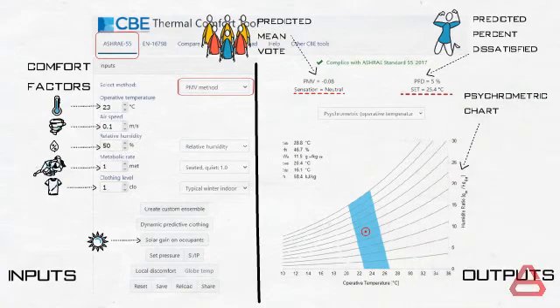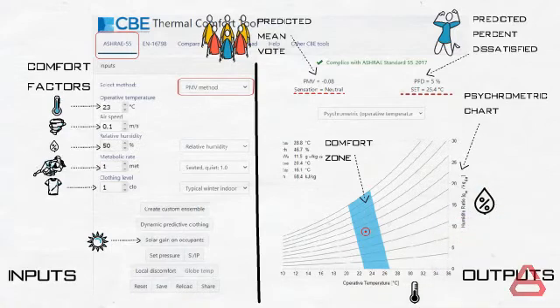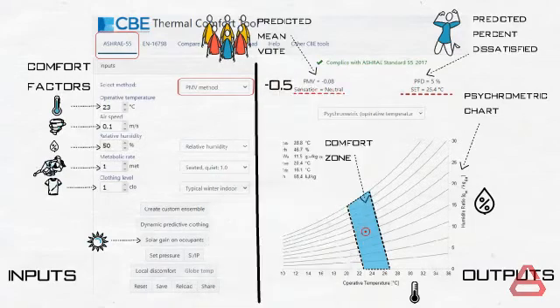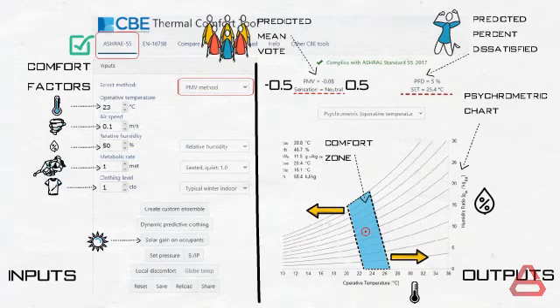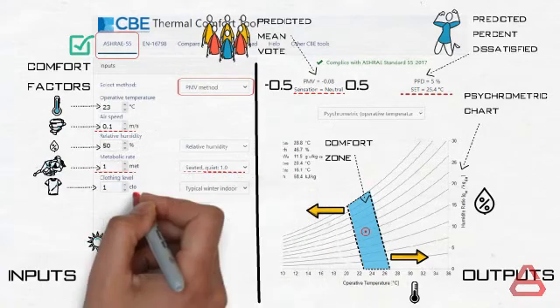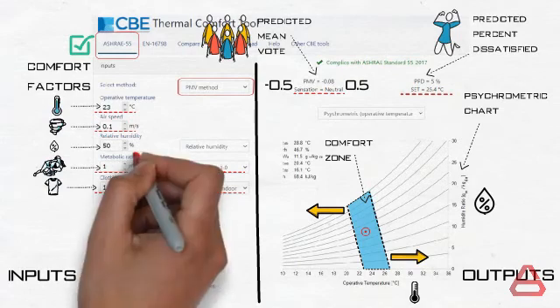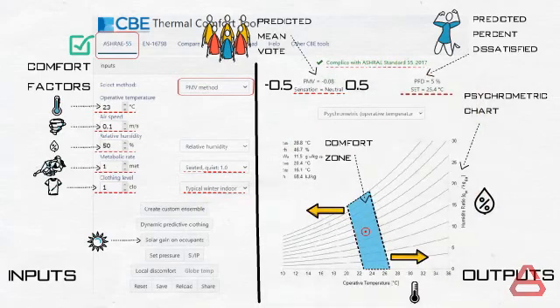This is a psychrometric chart showing the comfort zone highlighted in blue. The psychrometric chart shows air properties in graph form, most importantly dry bulb temperature and humidity. Any value of temperature and humidity inside the comfort zone and with a PMV between minus 0.5 and 0.5 complies with ASHRAE Standard 55. Changing the input variables causes the comfort zone to shift to the right or left depending on the new values. For the case shown, with an airspeed of 0.1 meters per second, a seated activity level, and typical indoor winter clothing, the operating point at 23 degrees Celsius and 50% relative humidity is compliant with ASHRAE Standard 55.